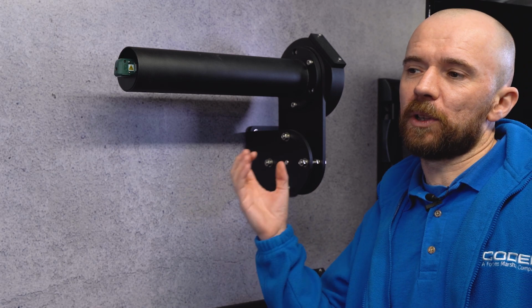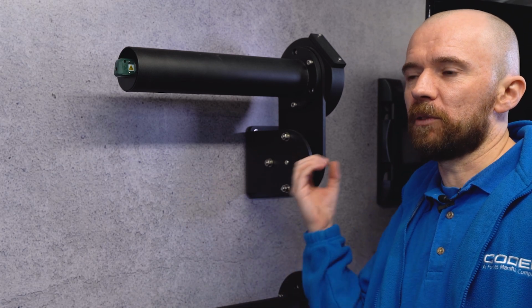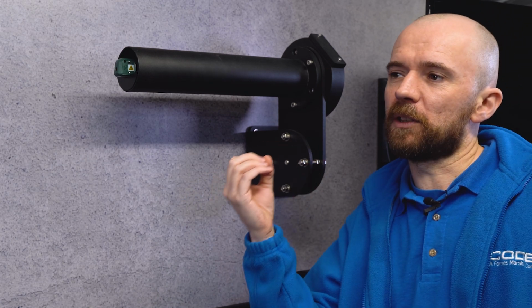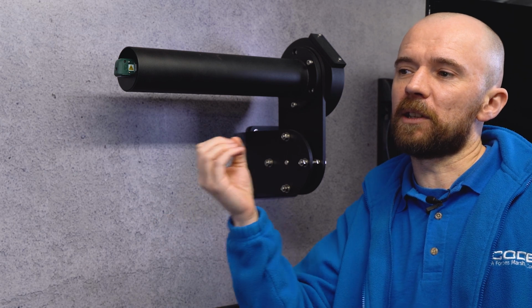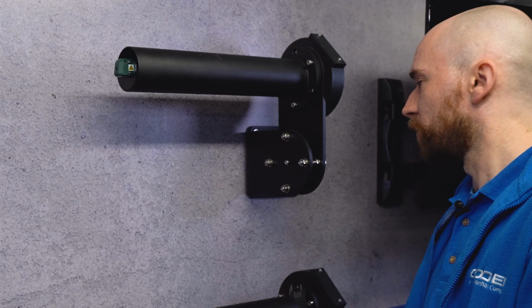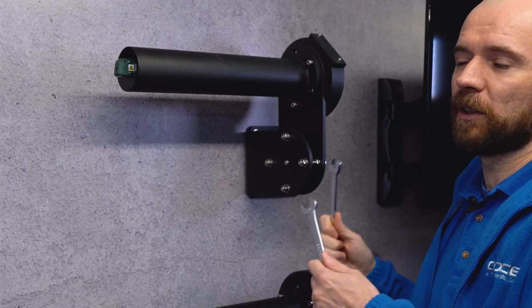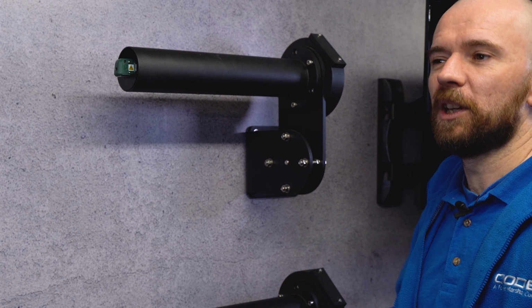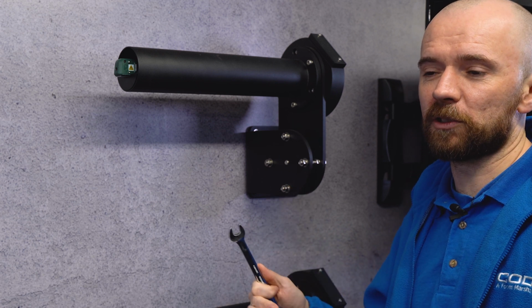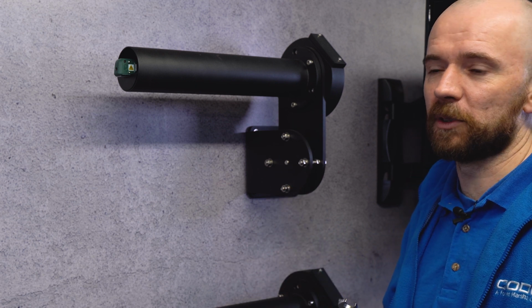At this stage, we're going to repeat the process at the mirror end, with the aim being to get the laser to be hitting in between all four of the lenses on the sensor head. Again, we do the vertical plane and the horizontal plane separately, and again, if we're going to make an adjustment, we loosen off the opposite alignment stud.